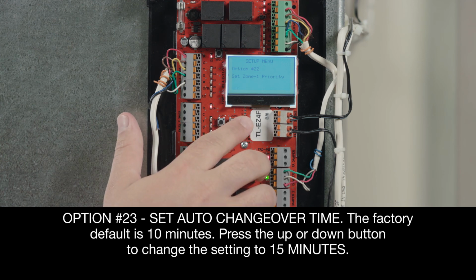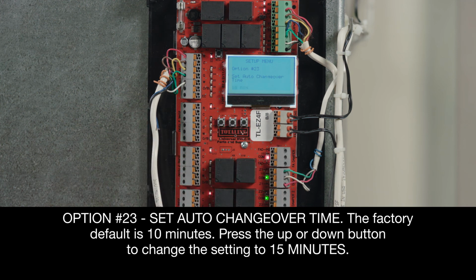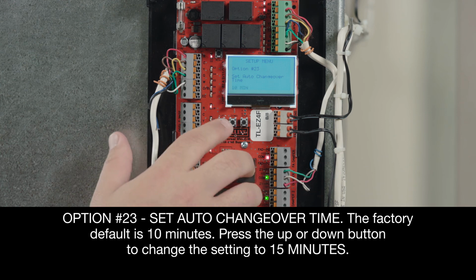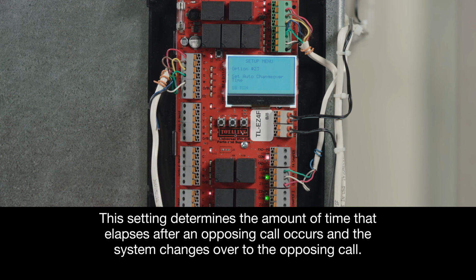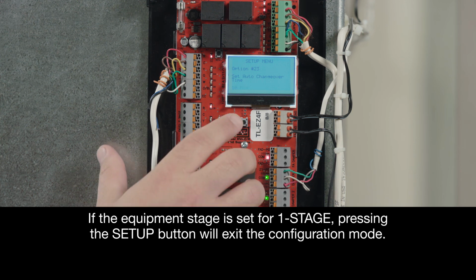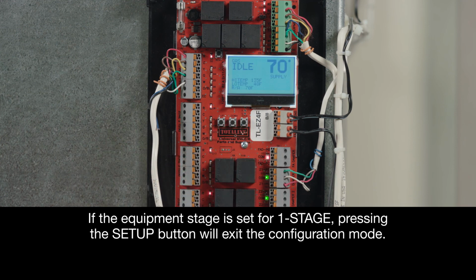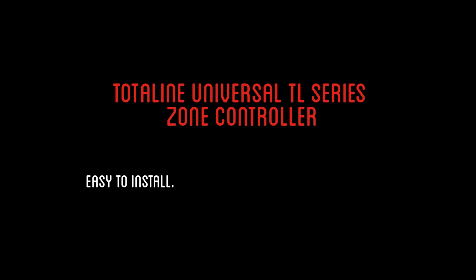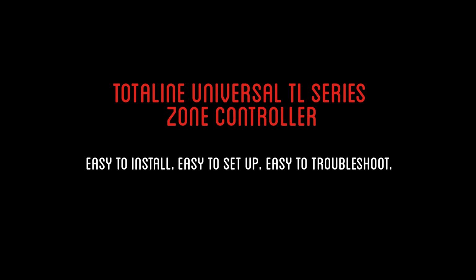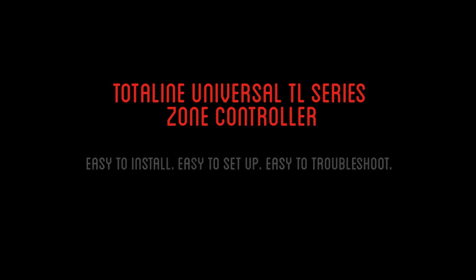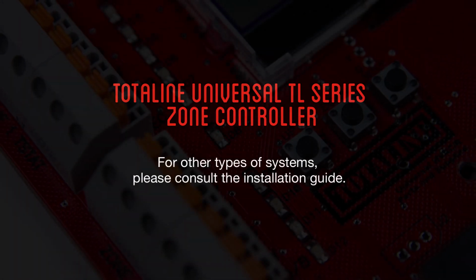And finally, let's go to option number 23, Set Auto Changeover Time. The factory default is 10 minutes. Press the up or down button to change the setting to 15 minutes. This setting determines the amount of time that elapses after an opposing call occurs and the system changes over to the opposing call. If the equipment stage is set for 1 stage, pressing the Setup button will exit the configuration mode. And that's it. Our new Totaline Universal TL Series Zone Controller is completely installed and set up, and the whole process was incredibly quick and easy. This demonstration featured an AC gas furnace system setup and configuration. For other types of systems, please consult the installation guide.